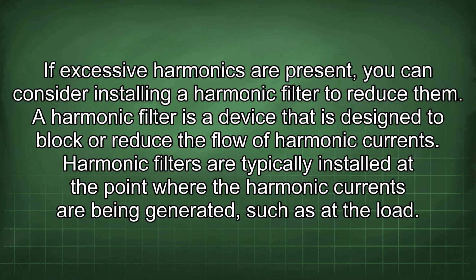If excessive harmonics are present, you can consider installing a harmonic filter to reduce them. A harmonic filter is a device that is designed to block or reduce the flow of harmonic currents. Harmonic filters are typically installed at the point where the harmonic currents are being generated, such as at the load.